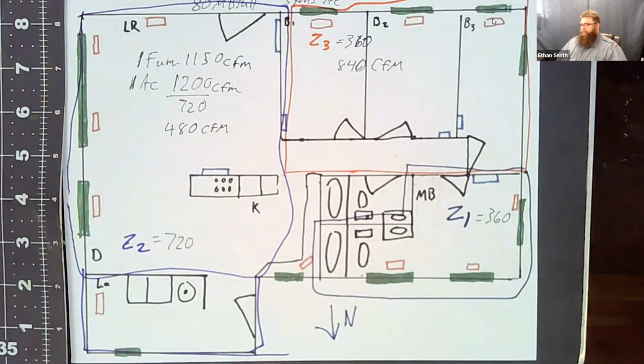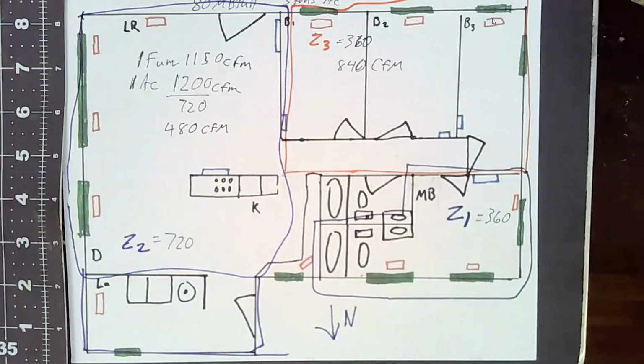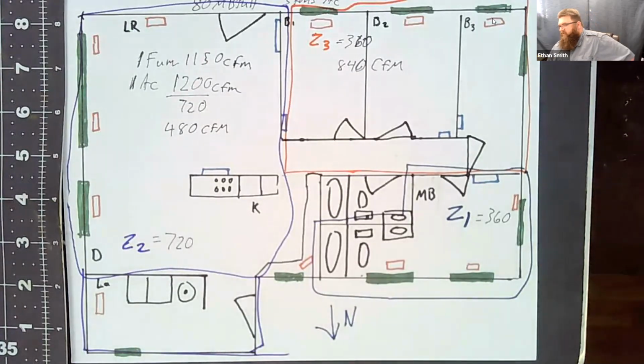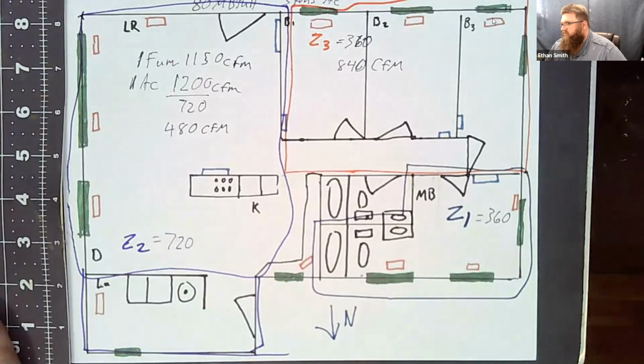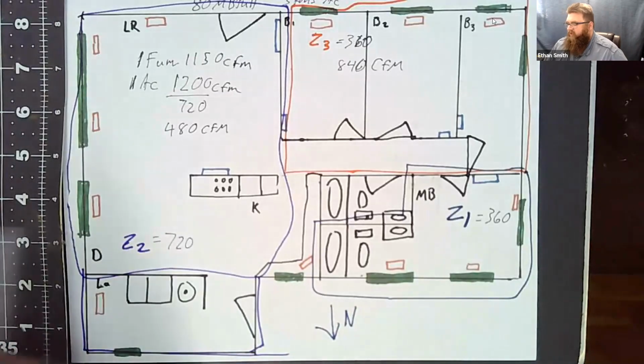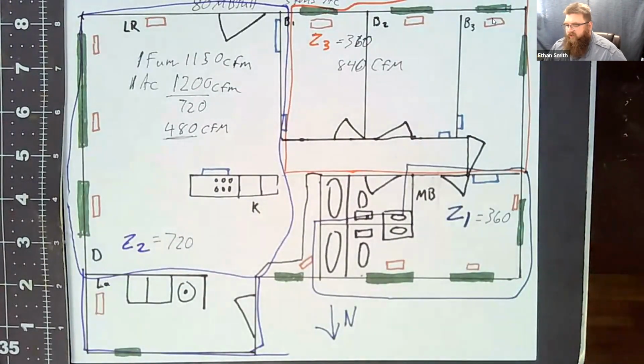What do you guys think? Combine zone 3 and zone 1. Okay, so combine the bedrooms and the master bedroom. That'd give us 720 CFM in that one and 720 in the front. So that's better. We've only got 480 CFM if we combine these two zones. When either of those two zones calls without the other one, we've only got a 480 CFM problem. So that probably could be dealt with. That's about a 30% excess air, 40% excess air. There are ways we could deal with that.